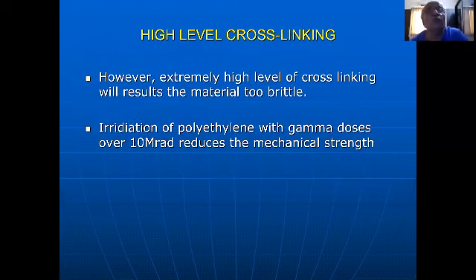However, an extremely high level of cross-linking will result in material failure and it becomes brittle. So our radiation has to be within the limit. Irradiation of polyethylene with a gamma dose over 10 megarad will reduce the mechanical strength. So we don't go much beyond between 5 and 7.5 megarad. That is the value we use for cross-linking this polyethylene material.